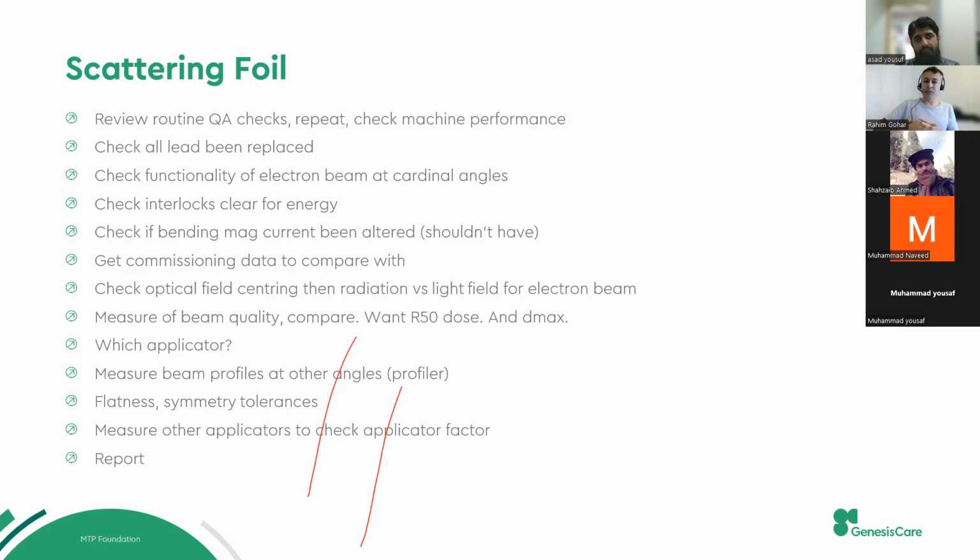Definitely then you compare your commissioning data. You have to set the baseline. If you have changed, you must have a baseline, measure it, compare to baseline, and the rest, factors, cutout factors, whatever, just take some of the subsets and compare.